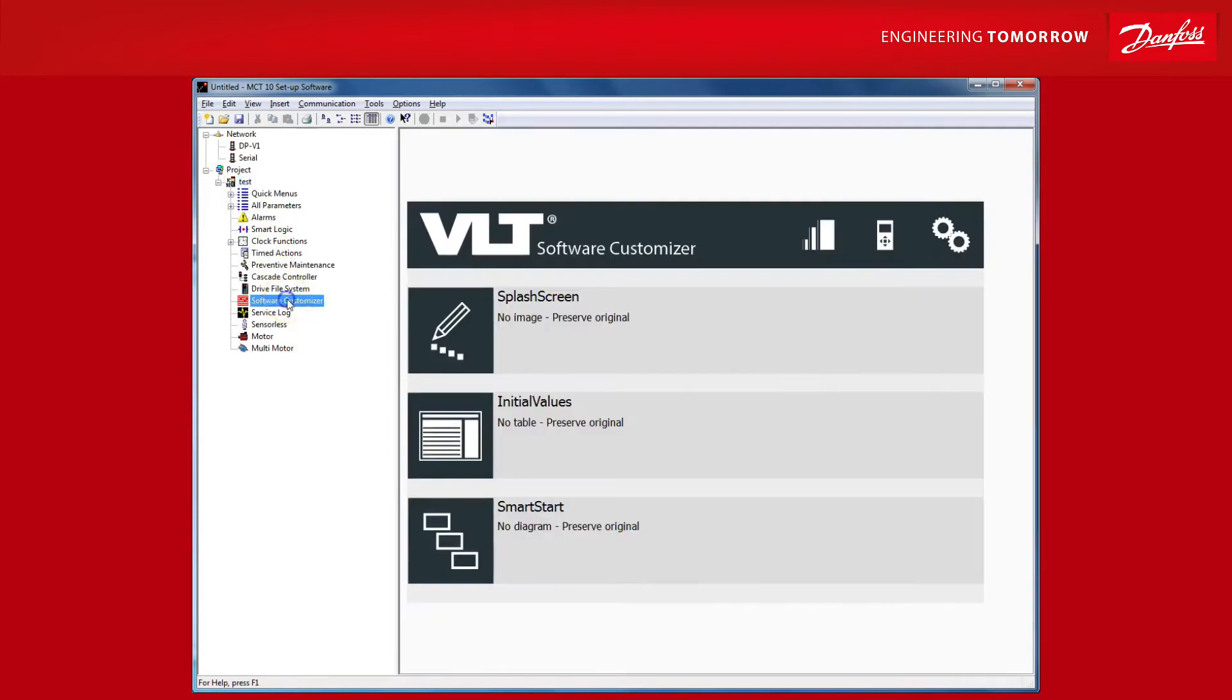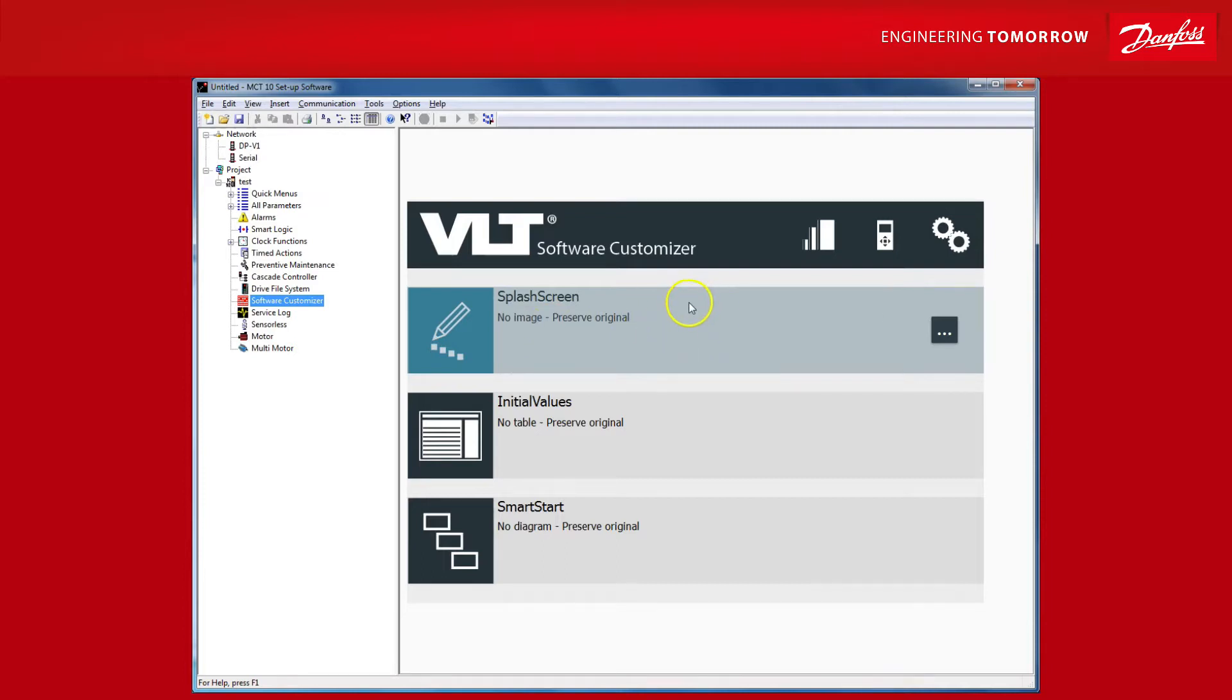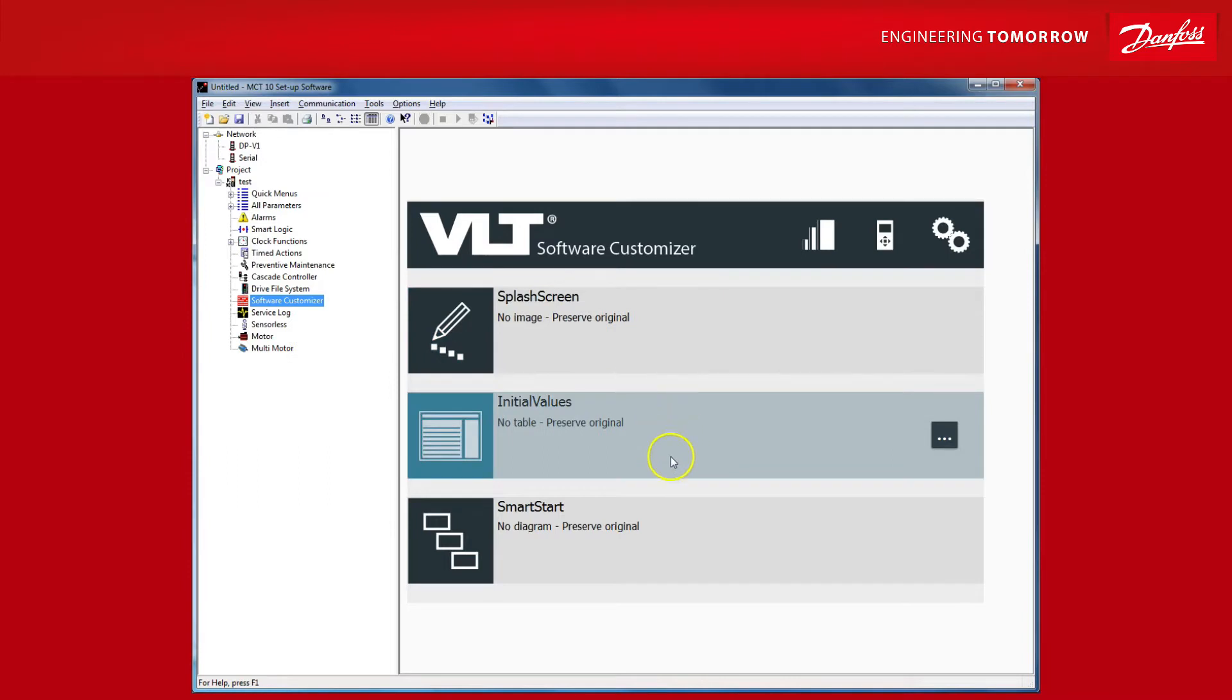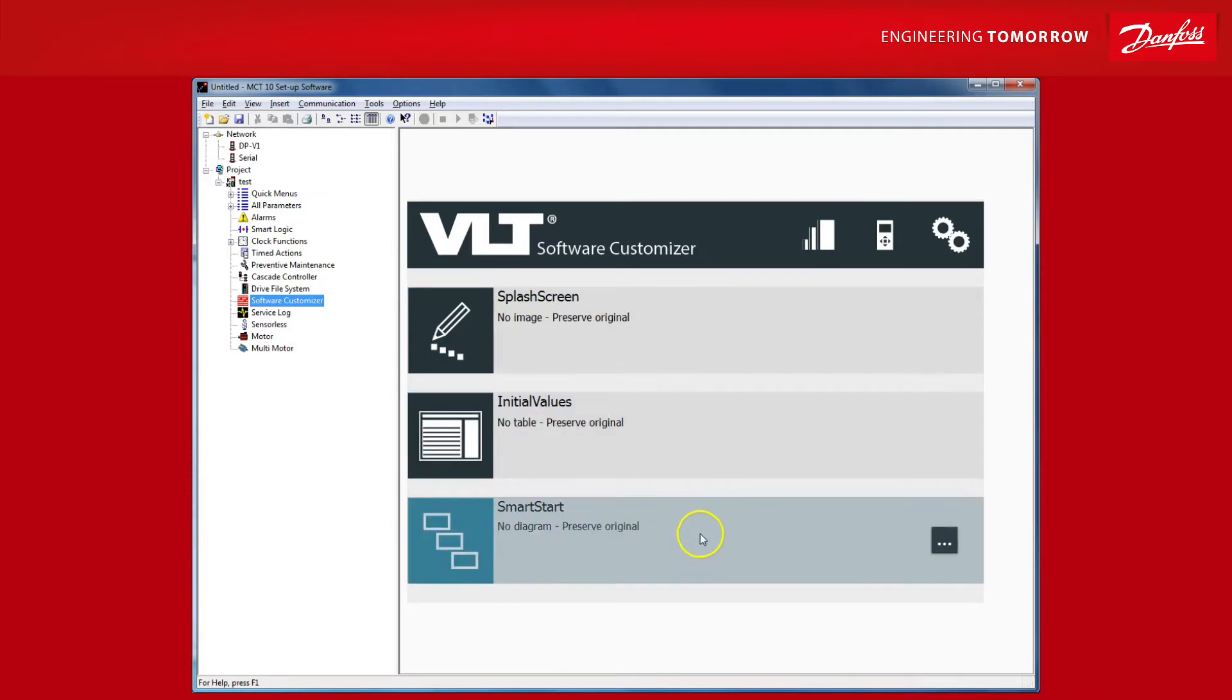Now you can select the VLT software customizer and you see the three main features. You can create a custom splash screen for when the drive is powered on. You can choose new default values for the initial drive startup. And finally, the smart start editor which allows you to create a completely custom startup wizard allowing you to choose which parameters are most relevant for commissioning your specific application.